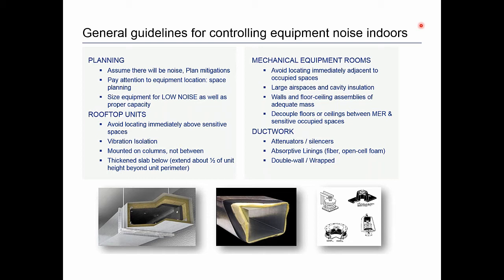For mechanical equipment rooms — having all large noise-making equipment inside the building — again avoid locating those rooms near occupied spaces. Use large air spaces and cavity insulation in the walls, ceilings, and floors surrounding the equipment room. Make sure your wall and floor-ceiling assemblies have a lot of mass to break that path, and decouple the floors and ceilings between a mechanical equipment room and any sensitive occupied spaces. Pay a lot of attention to your ductwork: use attenuators and silencers if necessary, use absorptive linings along the main duct path, and if you have breakout noise issues from thinner-gauge ductwork, there are products available to wrap the ductwork and absorb and block the sound.